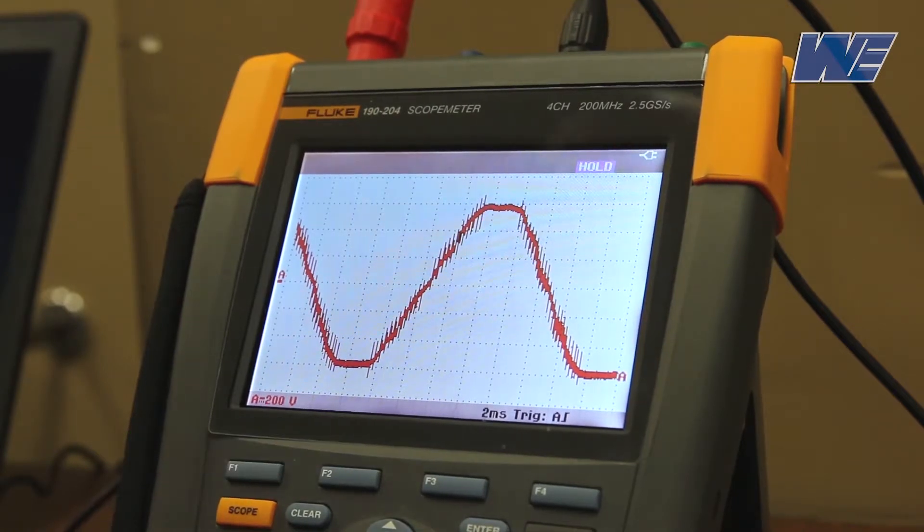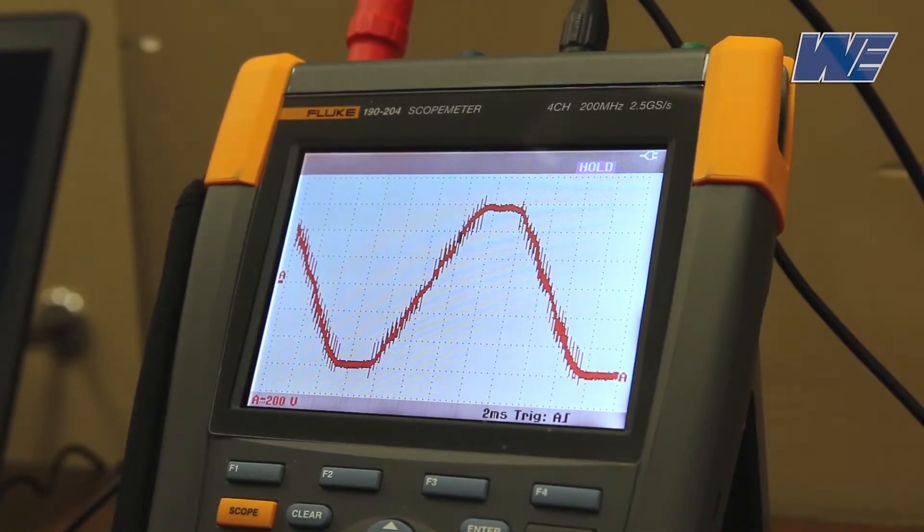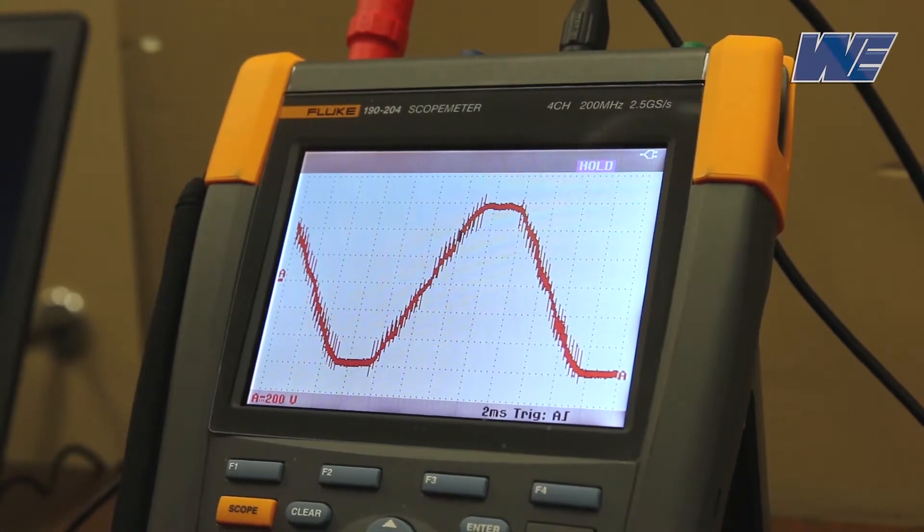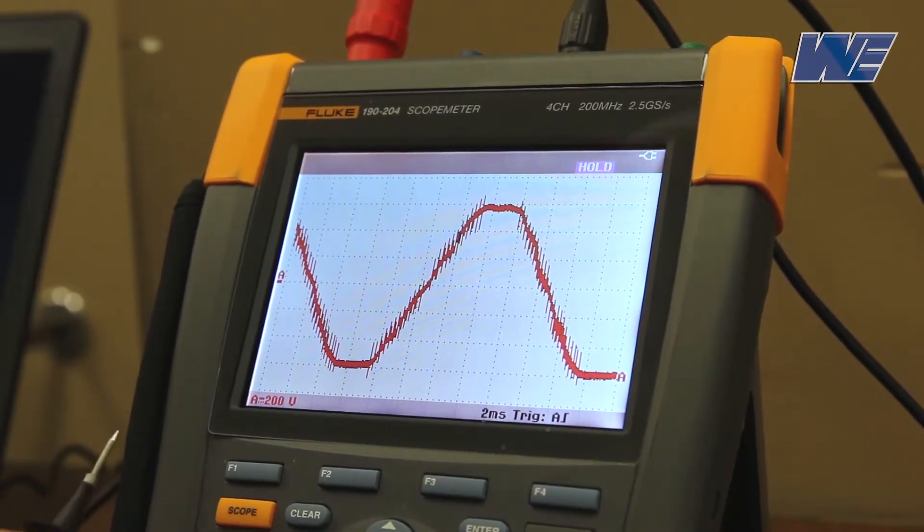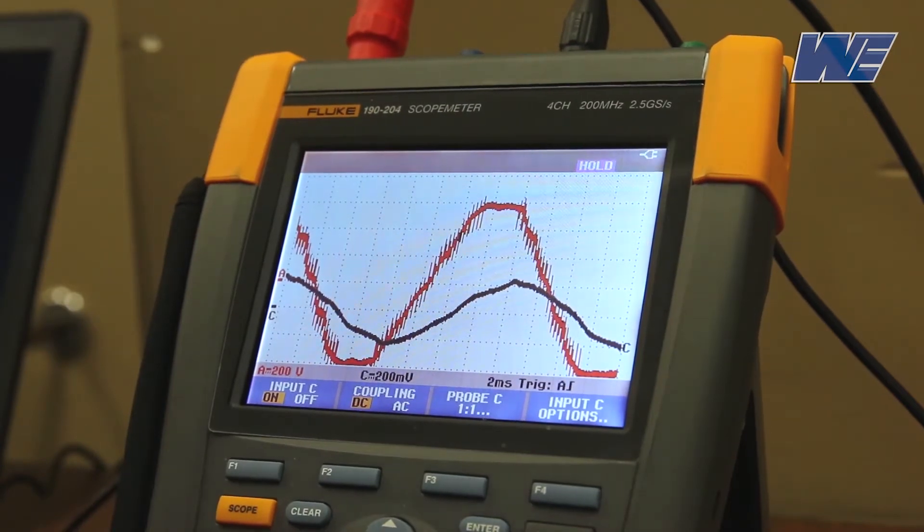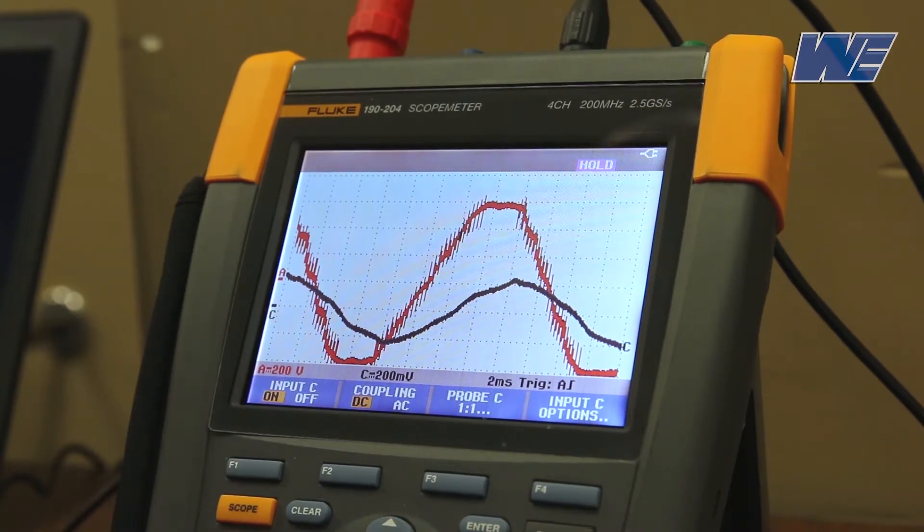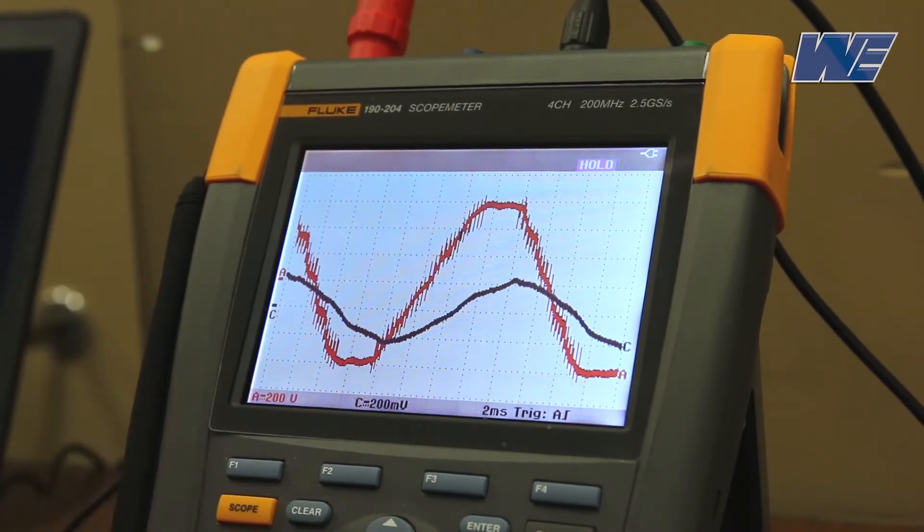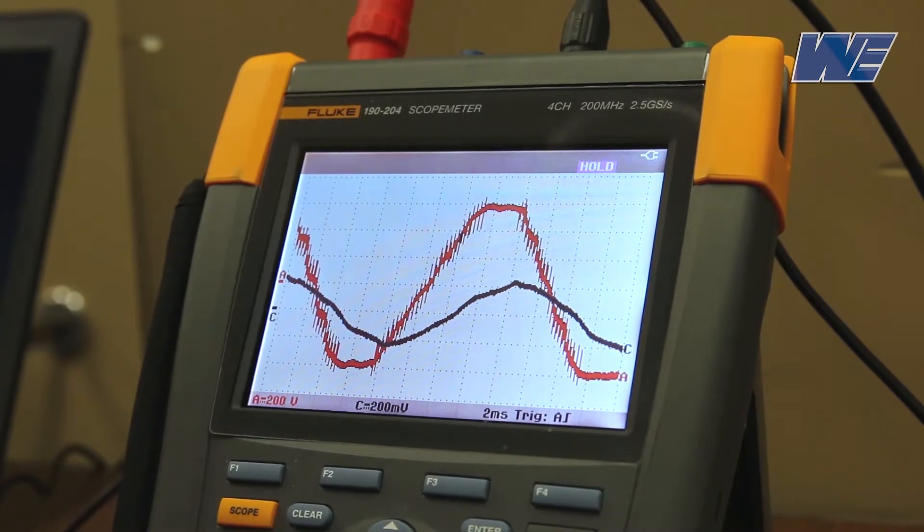You can see that the output voltage is now much more sinusoidal than the previous pulse width modulated outputs. I'll bring in the output current so we can look at that also. You can see that the output current is still fairly sinusoidal. The motor acts somewhat like a low pass filter for the current waveform.